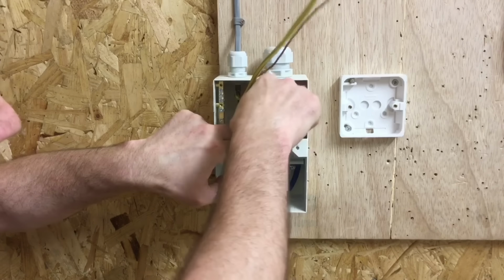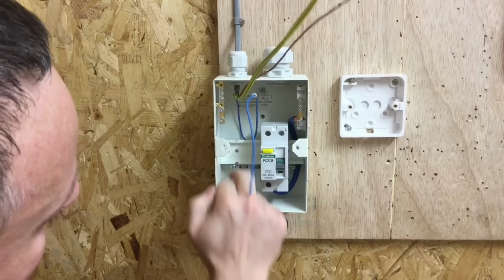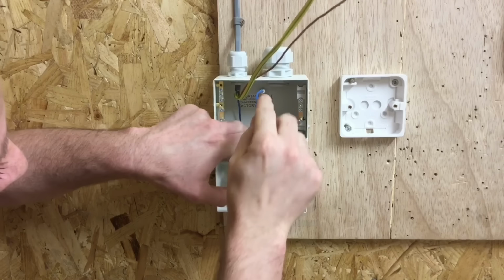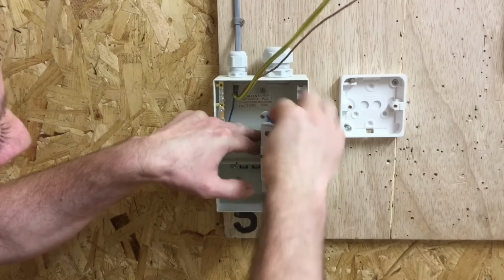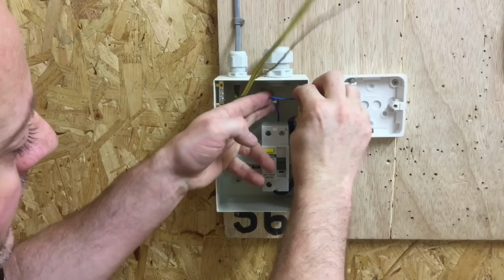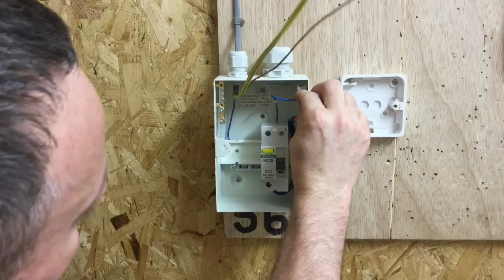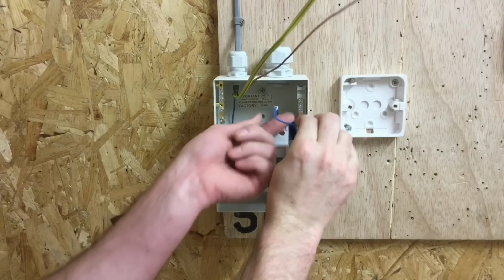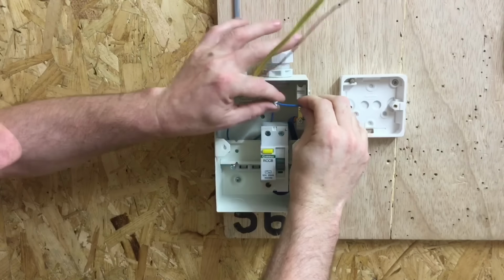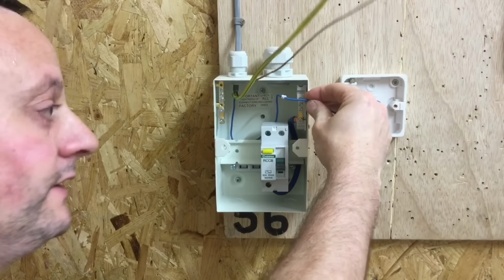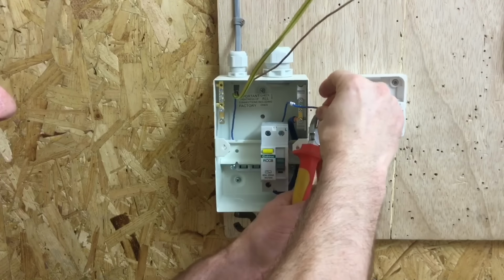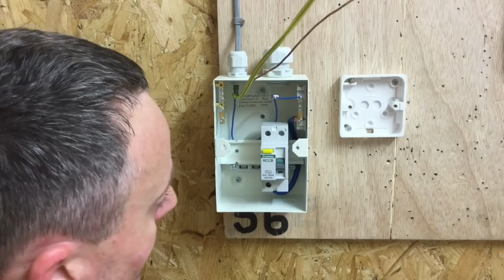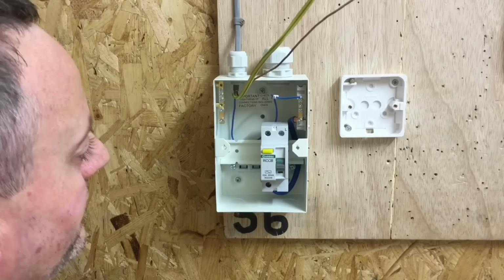It's going to sit along the bus bar at the back here, which it can't go below in this Crabtree design. So I'm going to sit it along there, along the back, and then I'm going to kick it round so it can be connected into my neutral bar. Must make sure I can still see the number 1 at the termination point, and I'm going to cut the conductors just there. And as always, we're going to double over our terminations.